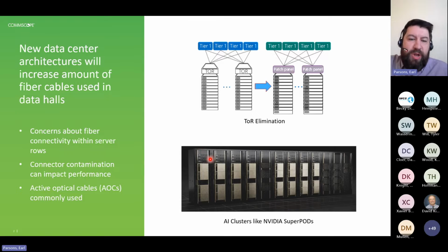And these racks do not have a top of rack switch. Instead, there's only 4 servers in each rack, and they are connected to the first tier switches here in the middle of the row. So again, going from one rack to another to get to the first level of switching, that's too long for copper cables, especially if you're looking at 50G and 100G lanes or even faster. So we need to go with a fiber connectivity between these GPU servers and the first level switching.